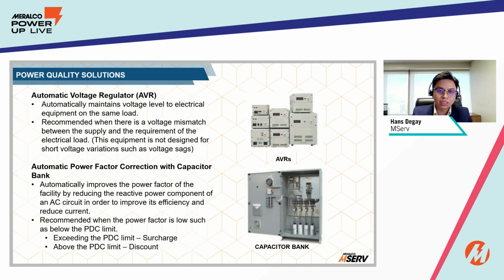It should be noted that voltage mismatch actually affects the relay setting, as they are more sensitive to tripping if there is a voltage mismatch. This was also discussed by the previous speaker. Na yun nga, kung ginamit niyo po is 380 volt equipment on a 400 volt system, your relays might have been set by the supplier on the 380 volt system. So there may be frequent overvoltage detected by the OV relay that could cause tripping to your equipment. So it goes hand in hand that you need to regulate the voltage properly to the equipment levels and set the relays accordingly so that there would be no nuisance tripping.